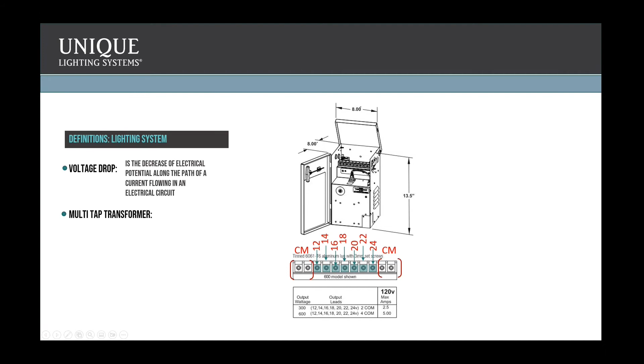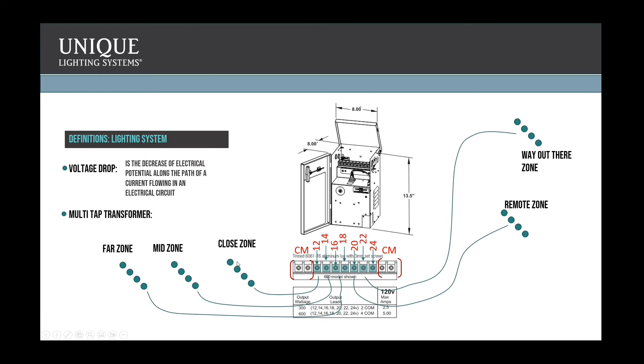A common way to think about these multi-tap transformers: in the field we'll always have a zone of lamps relatively close to our transformer, some mids, some remotes, and maybe a zone way out there. On that far zone, we have a really long run of wire coming back to the transformer, much longer than our close run. So we'll have a much larger voltage drop on that line than on the close one. We may need to start our voltage at a higher level to absorb this large voltage drop, so that our far zone and our close zone are burning at the same rate.